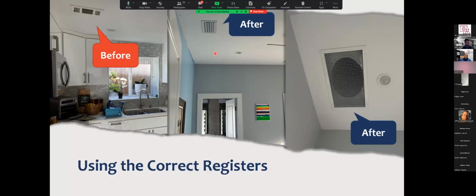And so typically, since we're putting much smaller systems in, we may have more face velocity here and more CFM, but since it's going across the roof, people aren't feeling it. But in some rooms, we have much less CFM, depending on what the unit is. So that active mixing is really important, and you get that with these type of registers.